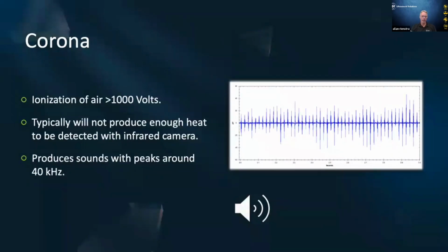Now, if we record that sound file with our ultrasonic data collector and then look at it in the time domain, as I've just shown here on the screen, what we start to see is these distinct peaks. And if we were to just listen for them, we can't hear them because they're happening too quickly. This whole time waveform, this is 1 second. So, all of these events are happening in a second. And if we were to bring it into the frequency spectrum, we would see that depending on where we are in the world, these peaks would either have 50 or 60 hertz deltas between them in terms of time. And that's just showing the line frequency, or the carrying line frequency, of the electrical system.